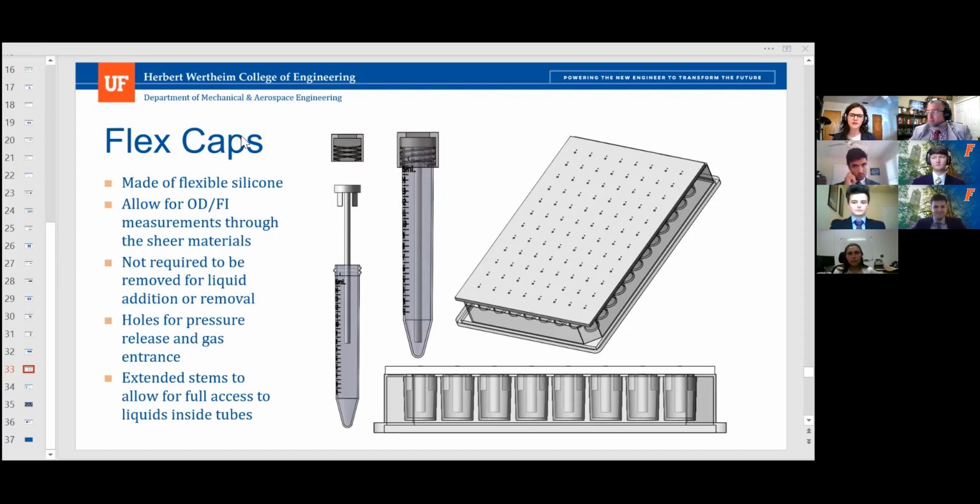To add fluid, the tip of the pipette is lowered to the hole related to the desired vessel and presses into the cap, deforming it slightly. This allows for the injection of fluids without creating aerosols.